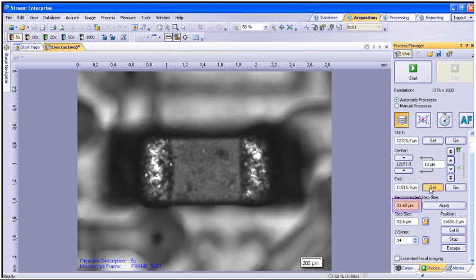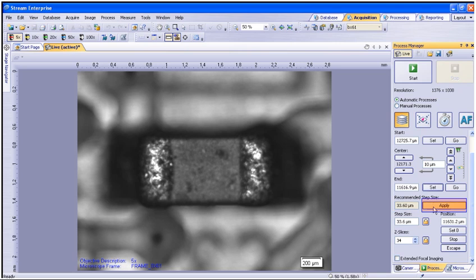You must verify the recommended step size value is set. If the step size is too far above the recommended step size, your image will come out with blur spots. You can hit the apply button to have it default to the recommended value. The software sets this value automatically based on the function of the objective lens numerical aperture. Once the step size has been determined, it will display the number of Z slices required for this magnification and Z range.